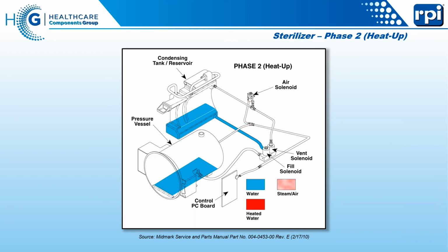Sir? Yeah, I had a situation like this. We had a dental site that had two of them side by side, right against the wall. And right when we picked it up, we were blowing boards, one after another. We diagnosed it and couldn't isolate it. Finally, they were running them so much and they were side by side that they were heating up on the board side, and it was just blowing boards. So we had to actually move them, and because of the cooling fan in the back, we had to give them enough space. Yeah, overheating is not usually the biggest problem. The biggest problem is relays that are just undersized. But yeah, that's not a good situation for them.